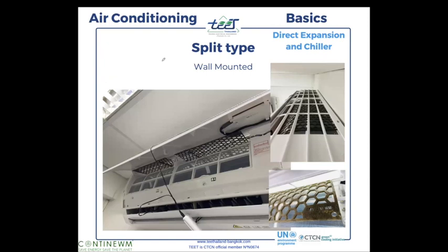Where to install Continewm? This is very simple. The closest to the coil as possible in the wall-mounted unit. In this case, we place it on the top of the filter. The reason for that is that there is no plastic protection enough to prevent the net from touching the coil, and the net should not touch the coil.